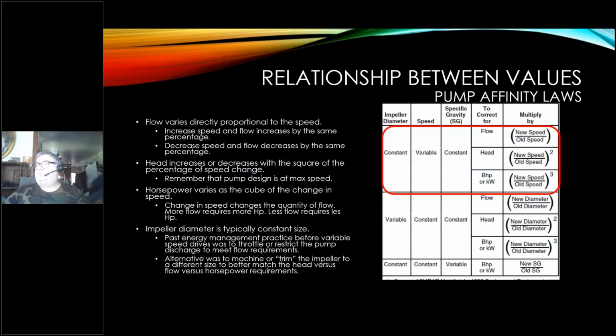Don't worry about this. Where we really get into the controversial part is the brake horsepower kW in variable speed. By the affinity laws, they say that if you change the speed, it will change the horsepower by the cube of the change. And we'll see this example coming up. Horsepower varies as the cube of the change of speed. The change of speed changes the quantity of flow, which makes sense. It would change the horsepower required. More flow requires more horsepower, less flow requires less. The impeller diameter is a constant size.